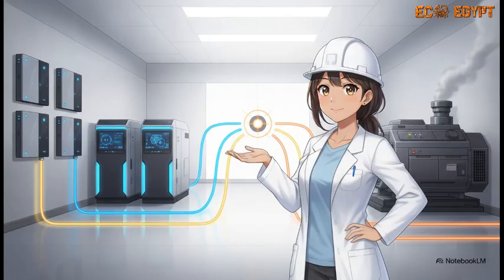Let's unpack the hardware stack that makes this hybrid system possible. To handle that 490 kilowatt peak of solar, we're using 4 units of Huawei 115 kVA solar inverters. That gives us 460 kilowatts of AC capacity. Then, for energy smoothing, the design integrates 2 215 kilowatt-hour BESS units, and acting as the ultimate safety net is a massive 500 kVA diesel generator. Getting these 3 totally distinct power sources to play nicely together is an absolute engineering marvel.